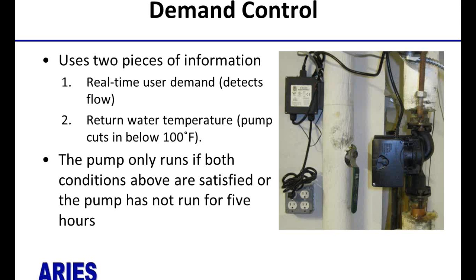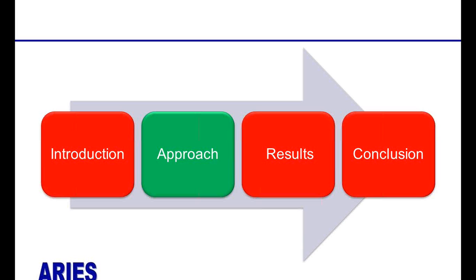Finally, demand control is a newer control strategy, and one that we tested in this study. It uses two pieces of information, real-time user demand based on a flow switch installed in the makeup water line, and return water temperature at the pump. And the pump will only run if there is demand and the temperature at the return is below a set point, typically around 100 degrees. Furthermore, the pump will run if it's been off for 5 continuous hours.